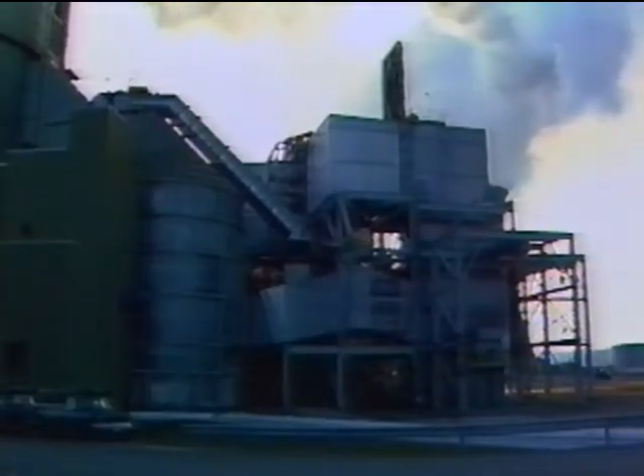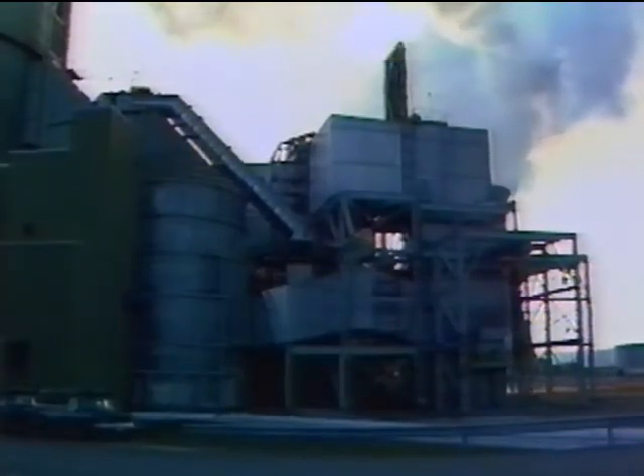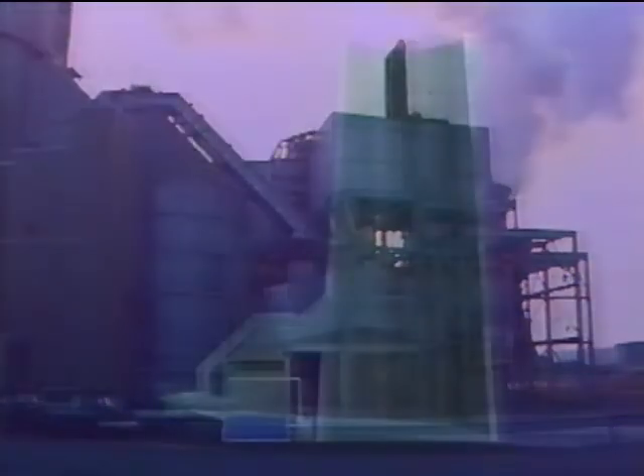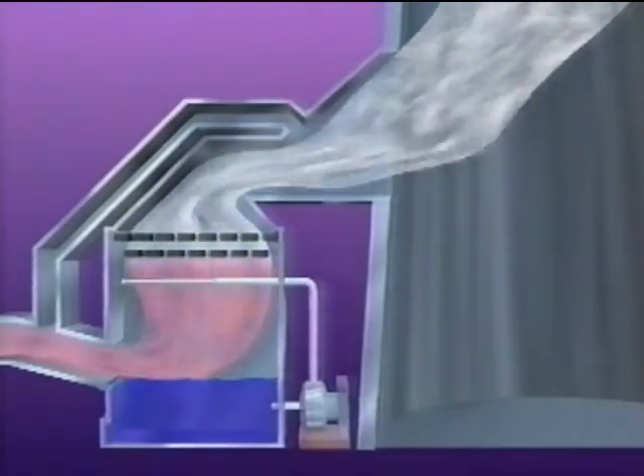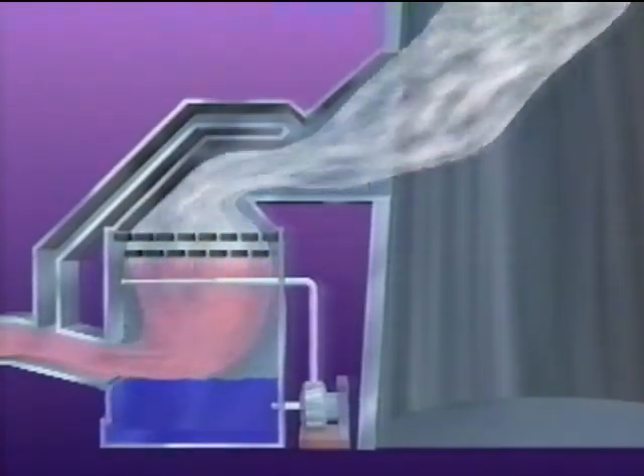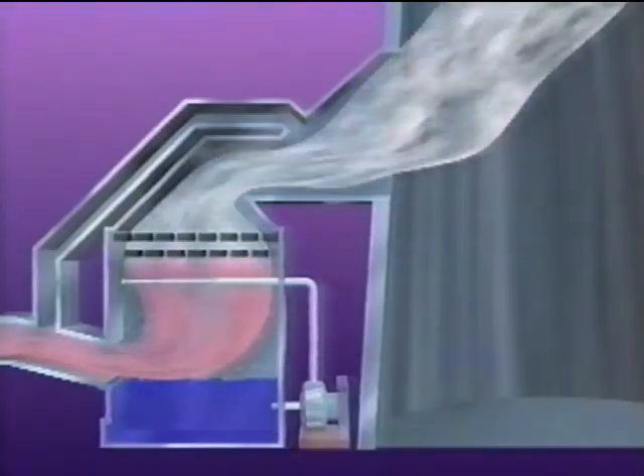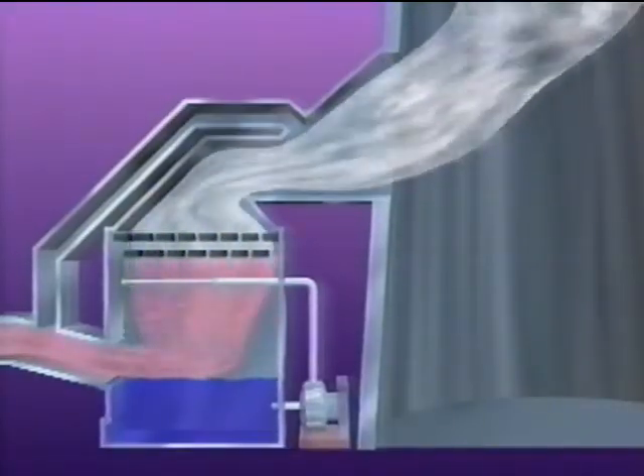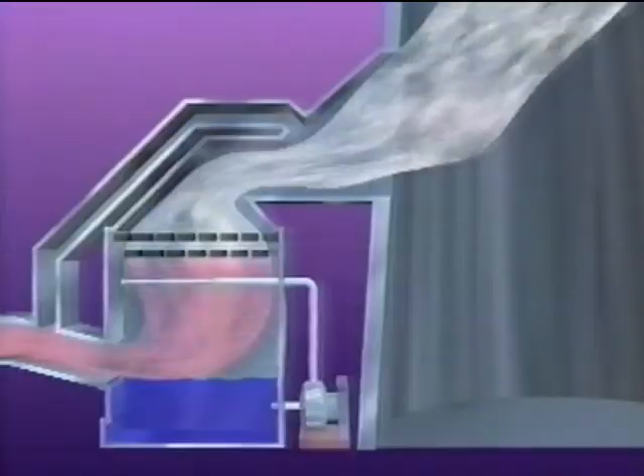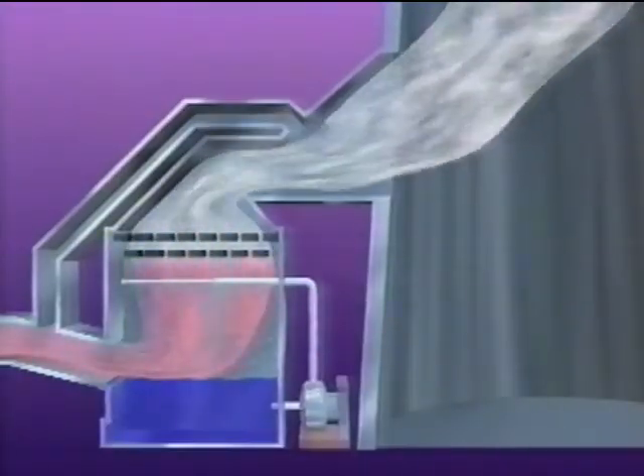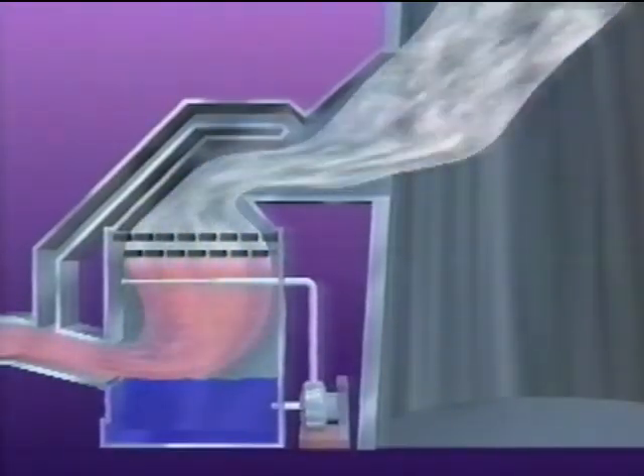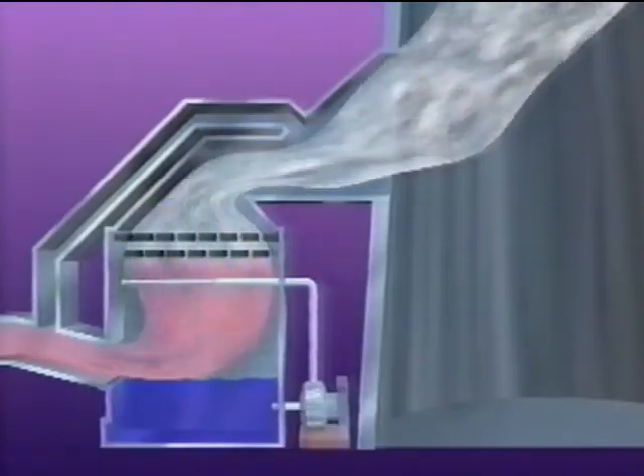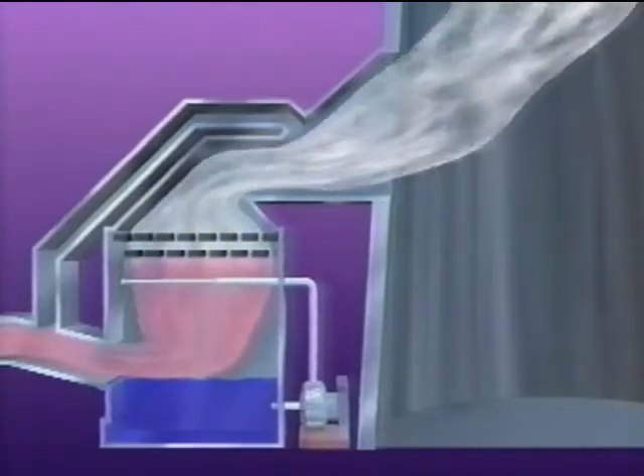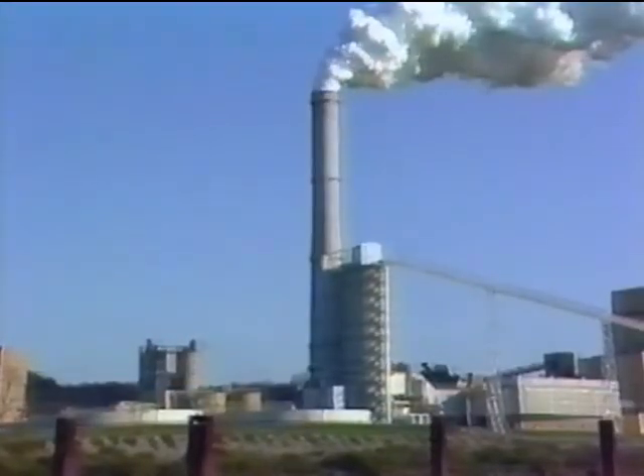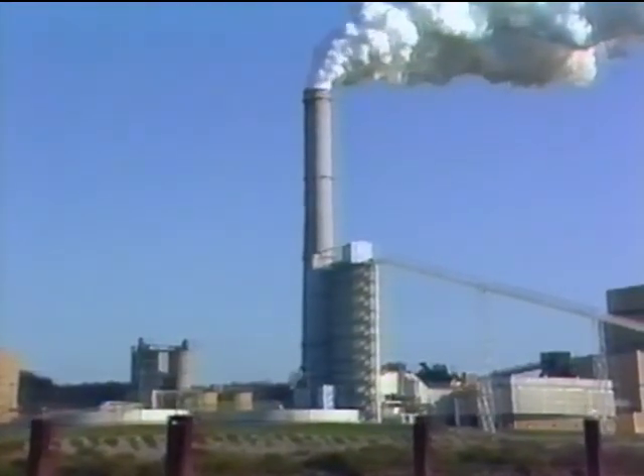The second unique environmental control here is the flue gas desulfurization system, which is known as the scrubber. Huge fans supply the scrubber system with gas from the precipitator. Lime slurry is sprayed into this flue gas in the absorber modules, where more than 91% of the sulfur dioxide, or SO2, is removed from the gas stream. The flue gas, along with almost 1,600 gallons per minute of water vapor, then flows from the scrubber to Zimmer's 573-foot stack.